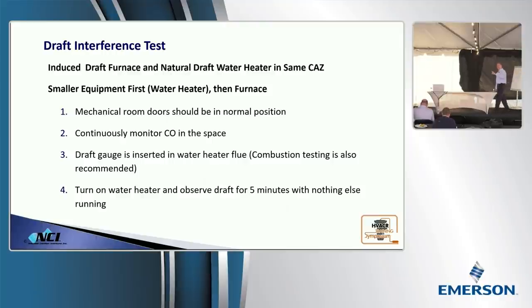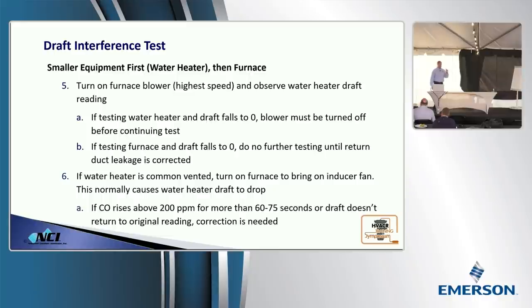You're checking draft. The first thing that you're going to do is you're going to kick on the biggest blower in the equipment or in the house, and typically that's going to be the furnace blower. The equipment has to run for a minimum of 5 minutes before you do this. Your draft should stabilize at that point. Kick the furnace blower on. If the furnace blower makes the draft drop, you've got return duct leakage and you need to find it and fix it. The draft should never go down. So if you see that draft drop, you got an issue.